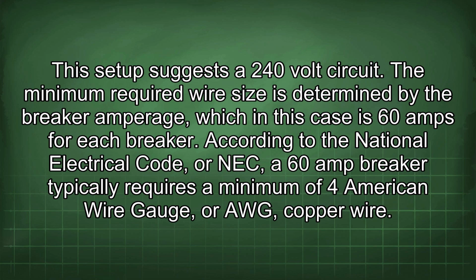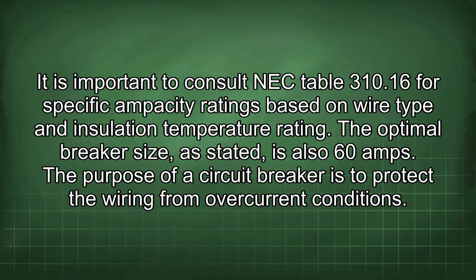The minimum required wire size is determined by the breaker amperage, which in this case is 60 amps for each breaker. According to the National Electrical Code, or NEC, a 60-amp breaker typically requires a minimum of 4 American wire gauge, or AWG, copper wire. It is important to consult NEC Table 310.16 for specific ampacity ratings based on wire type and insulation temperature rating. The optimal breaker size, as stated, is also 60 amps.